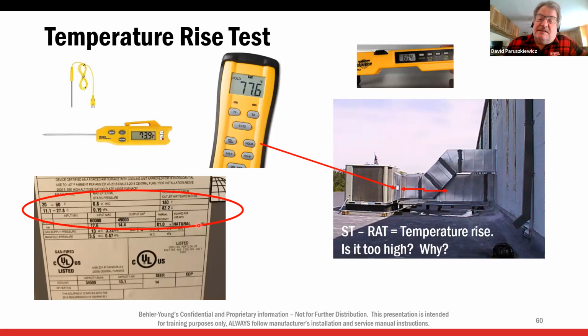So checking temperature rise, this is a really simple test. Now, back in the day when I started in the industry, this was part of our startup procedure. And for some reason, a lot of new techs don't do this. They haven't been taught to do this. This is a real simple test to see how the unit's doing. Very simple. We're going to read the return air temperature, get the heat running, get it nice and stabilized. We're going to check our return temperature. We're going to check our supply temperature. So in this case, I had a return of 60 degrees, and let's say I have a supply temperature of 100 degrees. So I have a 40-degree temperature rise.